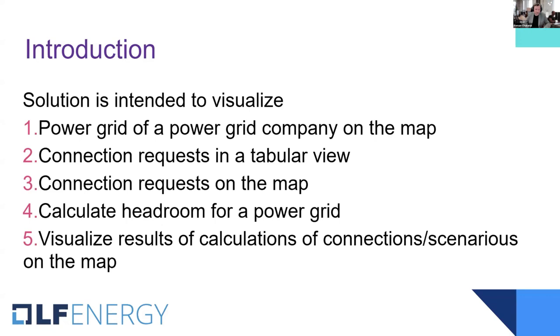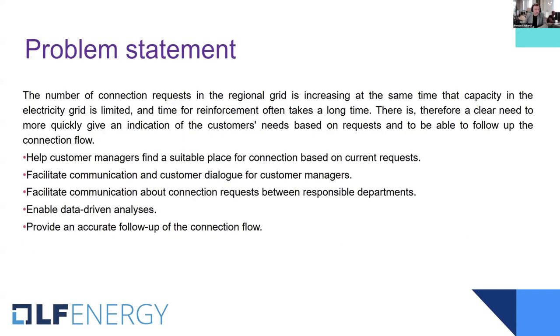What is also interesting with this solution is the following. Connections can be combined or clustered into scenarios. So you can calculate not only a single scenario connection to the power grid, but also a set of connection requests, including both types I mentioned, consumption and production. So, the problem statement.